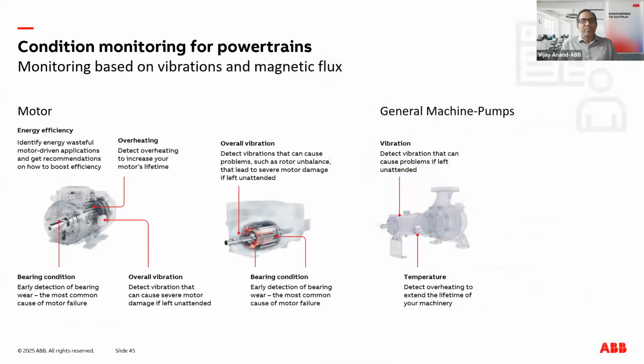When coming to the rotating equipment, such as motors, fans and pumps, what we use is the smart sensor, which is a cost-effective, battery-operated device that can be retrofitted on any motor or rotating equipment. The smart sensor has the latest sensor technology, which includes 3 different accelerometers in each direction of radial, axial, and tangential. It also has a magnetometer, an ultrasonic microphone for assessing bearing-related condition, and true machine skin temperature measurement. Even slight anomalies in the equipment condition can be detected at a very early stage using the smart sensor solution. Also, the sensor's mechanical design allows the transducers to pick up the true machine vibration independent of any resonances that may occur.